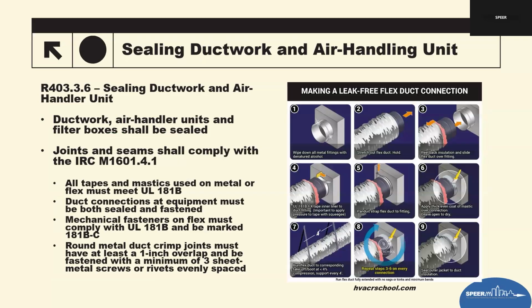And then sealing ductwork and the air handler unit. This is always brought up. I just like to put this on here to talk about how these are still a point of issue in getting ducts properly sealed. So 403.3.6 spells out what materials and fastening methods are required to properly seal duct systems. The requirements are important because duct leakage levels depend heavily on correct sealing practices. So all tapes and mastic used on metal or flex must meet UL 181B: UL 181B-FX for flex, approved pressure sensitive tape. Then you've got 181B-M, which is basically the approved mastic. If this isn't labeled, it basically does not comply. I don't know of any real mastic that's out there that's non-compliant. There may be some, but everything that I see does have the UL rating on it. But duct connections at the equipment must both be sealed and mechanically fastened.